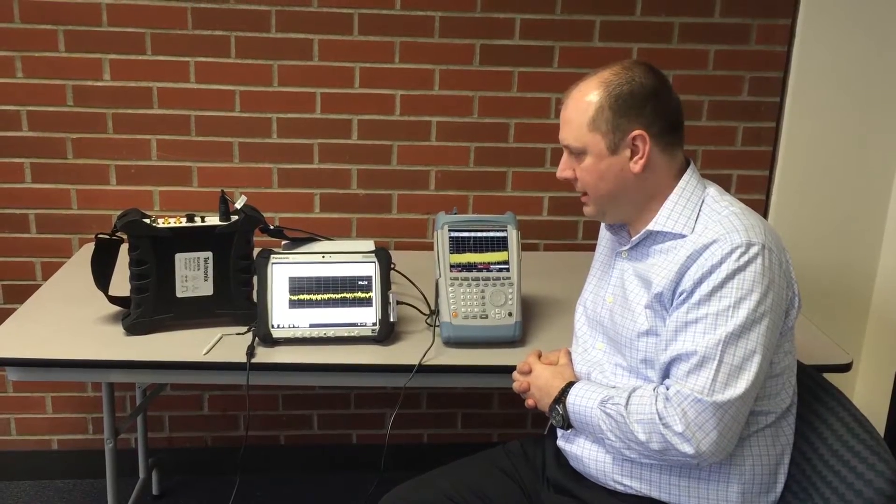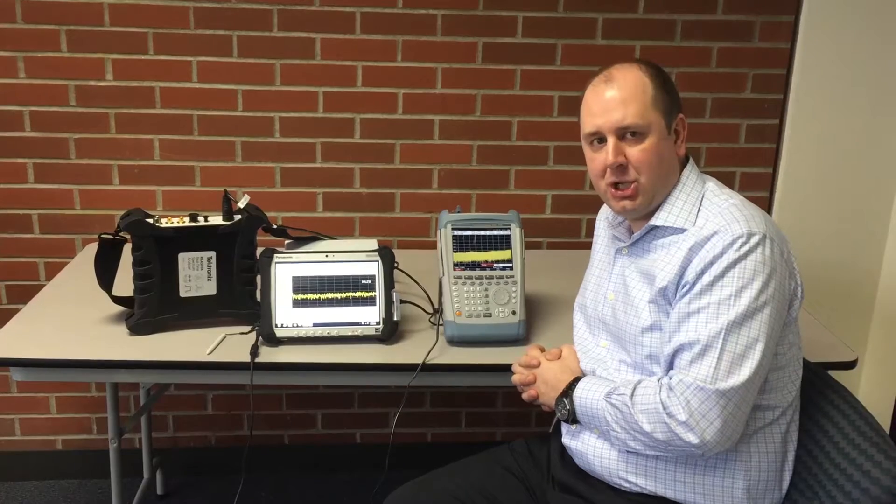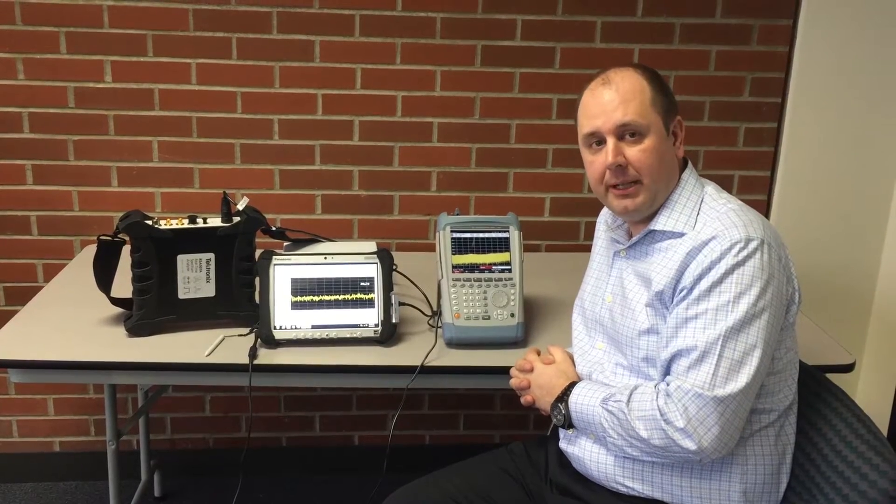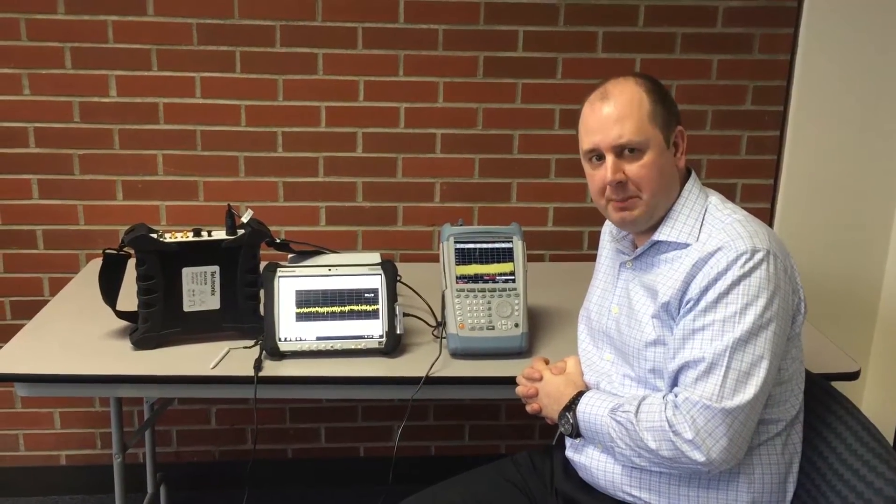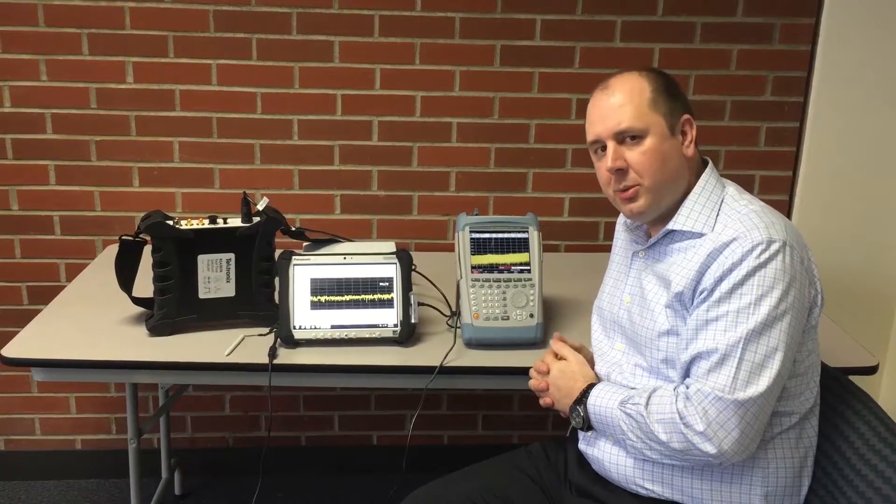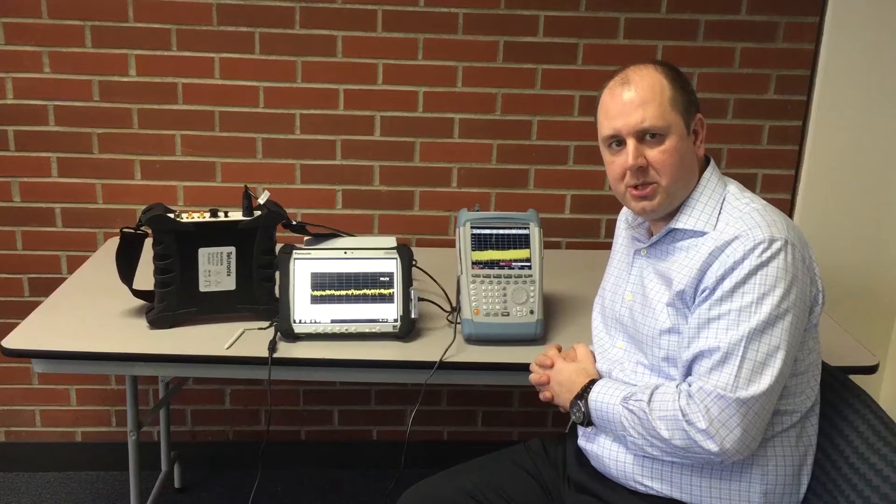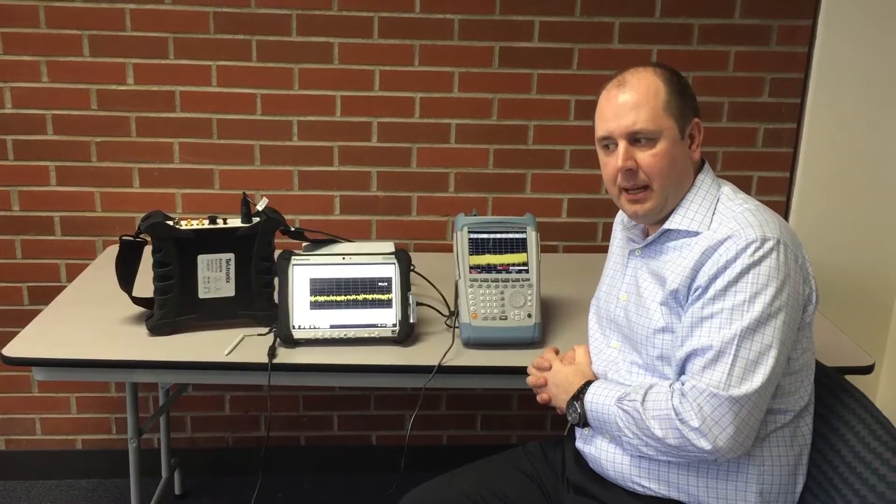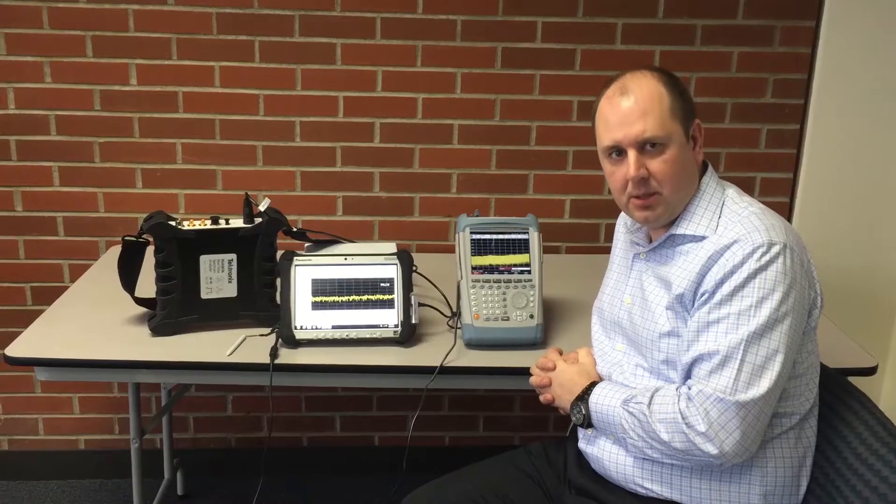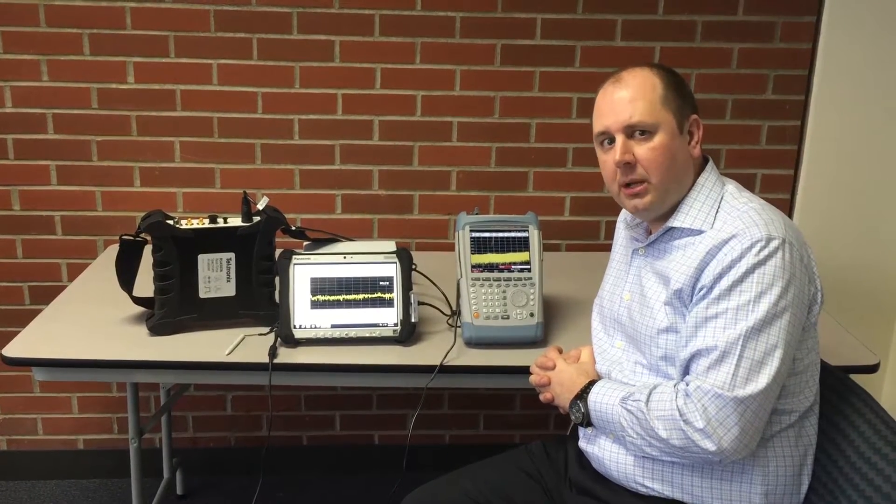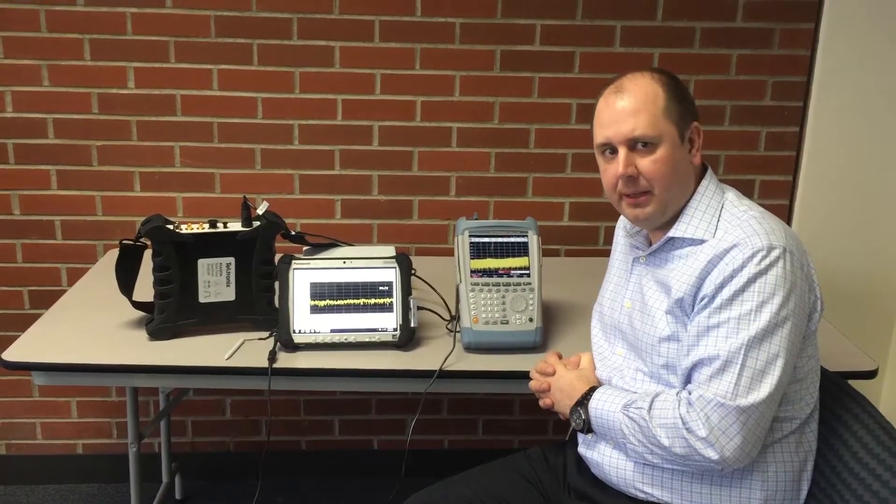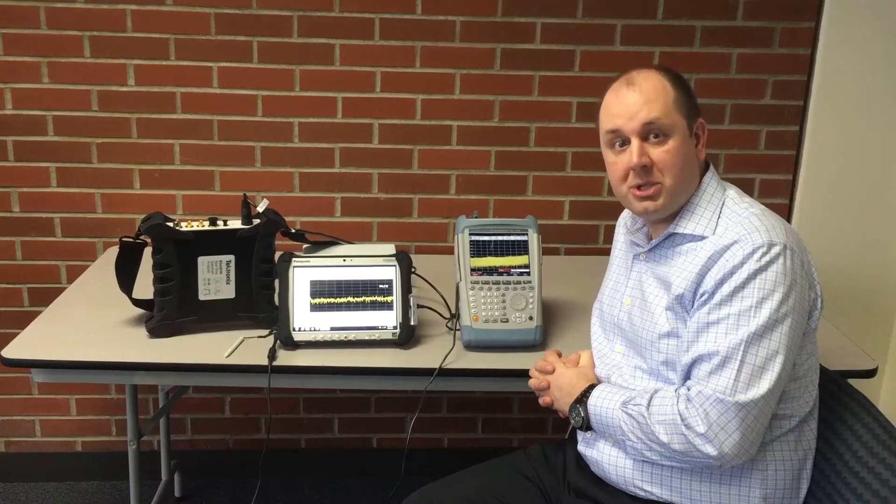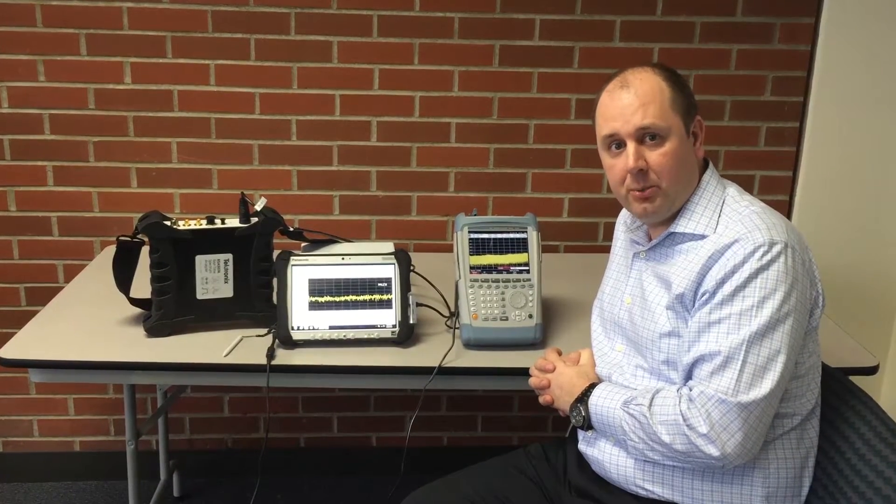We'll look at a comparison of the sweep speeds with a low RBW. The reason you would want to use a low RBW to do a sweep would be to get the lowest noise sensitivity on a measurement. When you're out in the field looking for low-level signals of interest, whether they be interfering signals or spurs, it's helpful to use a low resolution bandwidth.